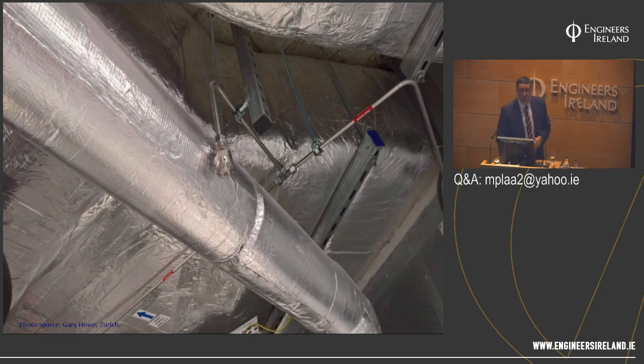What about that? Can anyone see what the issue is with that picture? Yeah? Obstructed nozzle. So you can see that 50% of that water mist is simply going to hit the side of that insulated pipework and be ineffective in a machinery space. Again, it was found due to a robust check on site of going into every single plant room, every single ceiling void, finding these things and getting them rectified. Again, I stress the point, the installer should have dealt with this issue. It shouldn't be up to the authority having jurisdiction, in this case me, the insurer, finding these things. So don't trust the installer always to get it right.